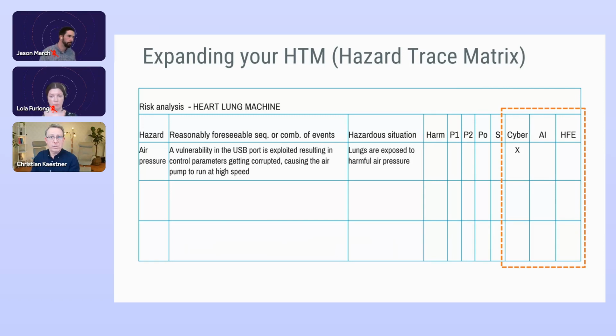Another approach when working with a smaller system is to expand a hazard trace matrix with additional columns, resulting in this example. So you can use check marks to highlight what type of risk you have identified. I hope you're familiar with this type of hazard trace matrix. We have a hazard, reasonably foreseeable sequence or combination of events. That's a long one. Hazardous situations, you have harm, and you have the probability and severity scaling. You can use check marks like I have done here. So to make this fly, I expect you to have additional documents such as data flow diagrams to capture a system from a security perspective. And to do this, you can get good food for inspiration in the playbook for threat modeling medical devices, which I think is valuable. I have a link to it on the screen.